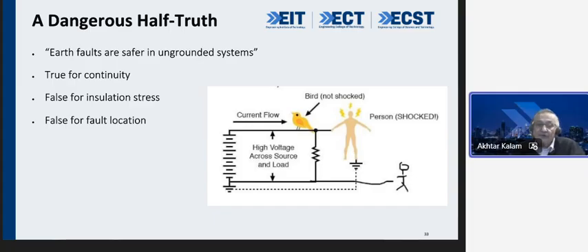It's a very dangerous half truth I want to talk about. And it's very interesting. You see that there's a bird on the tower or on the transmission line. Nothing happens to that bird. But when a person is sitting and touching the ground, you get a hell of a shock. Most probably you will die. But remember, earth faults are safer in an ungrounded system. It is definitely true for continuity. It is false for insulation stress, and it is false for fault location. Look at that simple bird sitting on the line. Nothing happened to that bird because there is no earth connection.